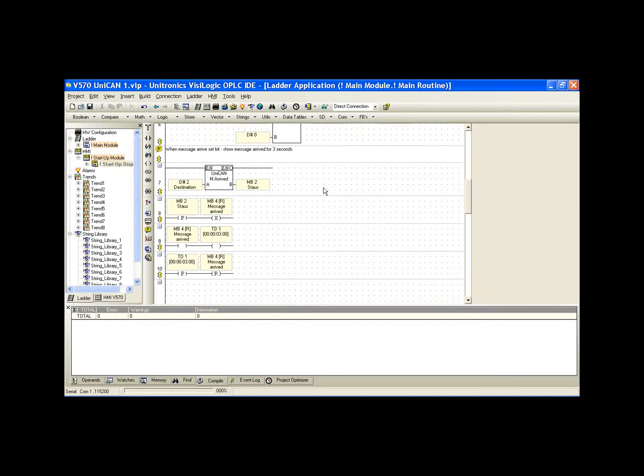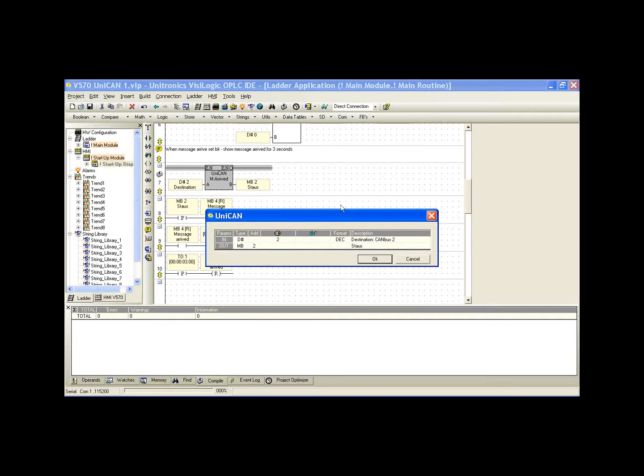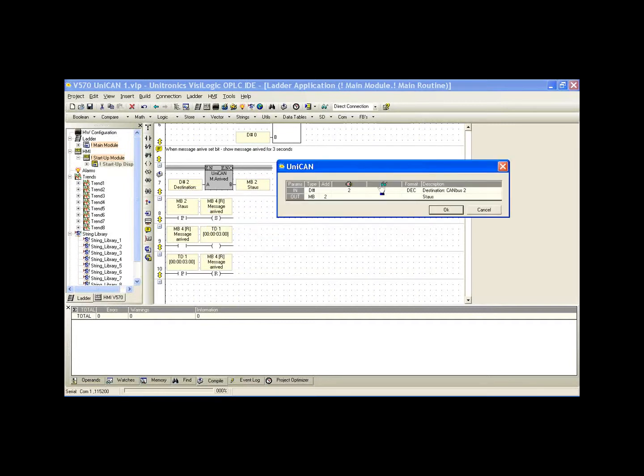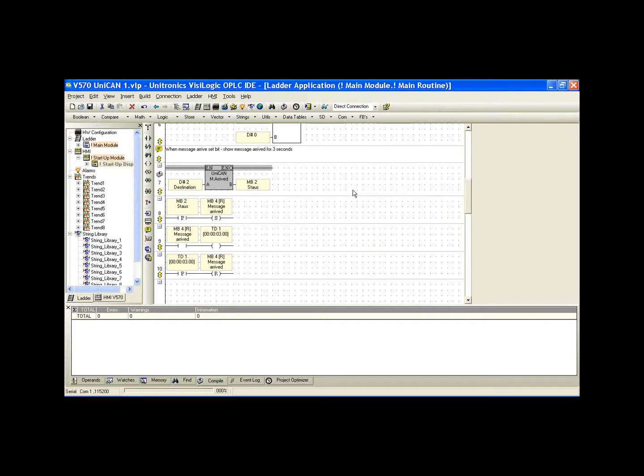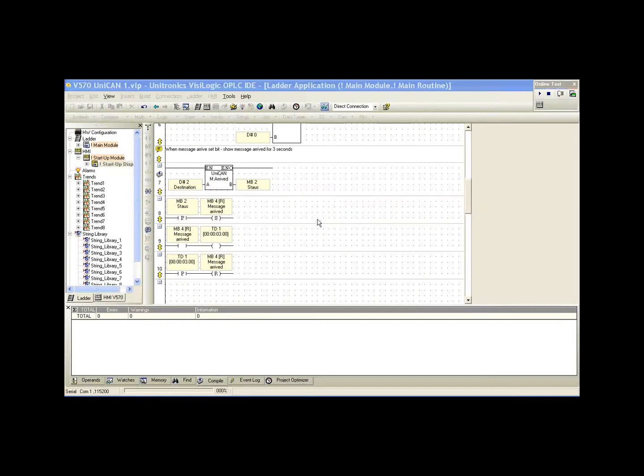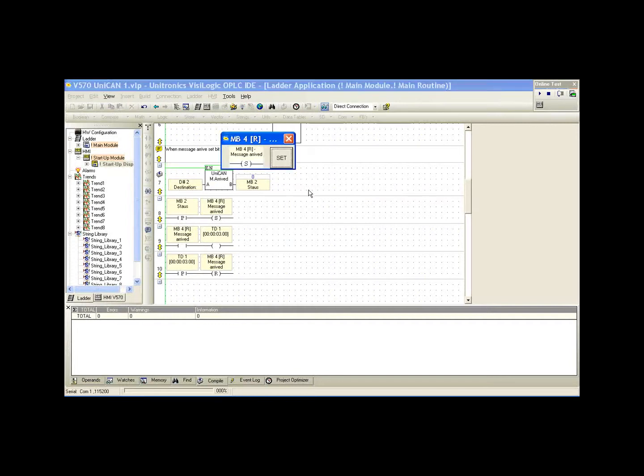If we look at the next function block, it's the UNICAN message arrived. We'll notice two parameters here. First is the controller we're interested in receiving a message from. In this case, it's CAN bus ID 2. The output is a memory bit that's going to go high. When we receive a message from ID 2, MB 2 will go high for a single scan. We can go ahead and we'll go online and take a look at this. I'm just going to send a message from controller 2. We want to see this bit goes high. And it does.